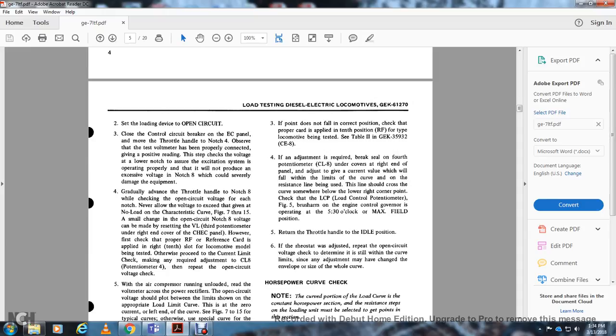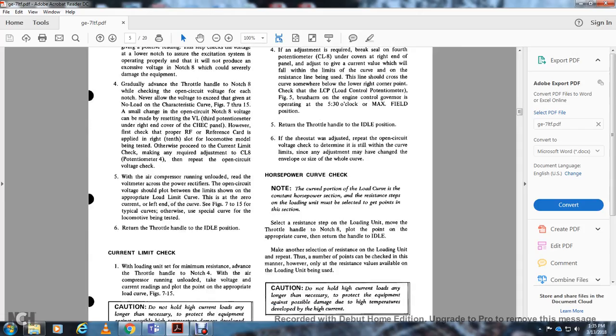If adjustment is required, break the seal on the potentiometer under the cover at the right end of the panel and adjust it to give a current value that will fall within the limits of the curve on the resistance line. The line should cross the curve somewhere below the low right corner. Also check the load control potentiometer, figure 5, with the engine control governor operating at the 5:30 o'clock or maximum field position. Return the throttle handle to the idle position. If the rheostat is adjusted, repeat the open circuit voltage check to determine whether it still falls within the curve. The sense of the adjustment may be checked against the envelope side of the whole curve.